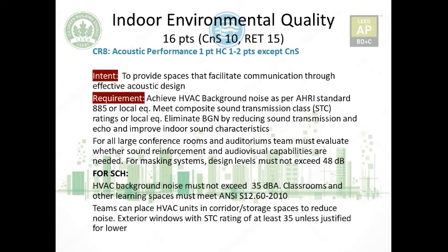Now when it comes to large conference rooms and auditoriums, they must first evaluate whether sound reinforcement and audiovisual capabilities are required or not, and if they are needed, they have to meet certain standards. And for masking systems, design levels must not exceed 48 decibels. Now, what is sound reinforcement? What is a masking system? We have to understand.